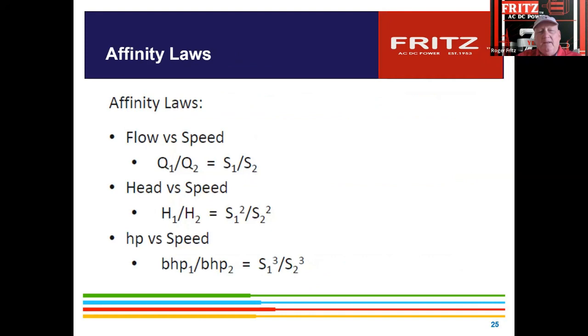These are the affinity laws. Flow versus speed ends up being more 1-to-1. Your head to speed is on more of a square factor. And then you've got your horsepower to speed, which is on the cube factor. So the head, meaning the amount of pressure it can produce, is about a 2-to-1 ratio, and horsepower is still a 3. So you can reduce speed, still produce pretty good head pressure in your system, and achieve this. So it ends up being a combination of total power saved.